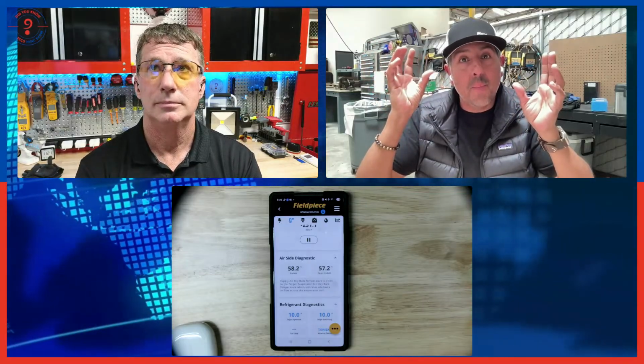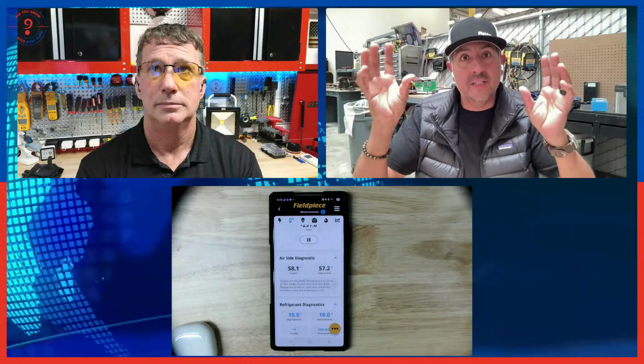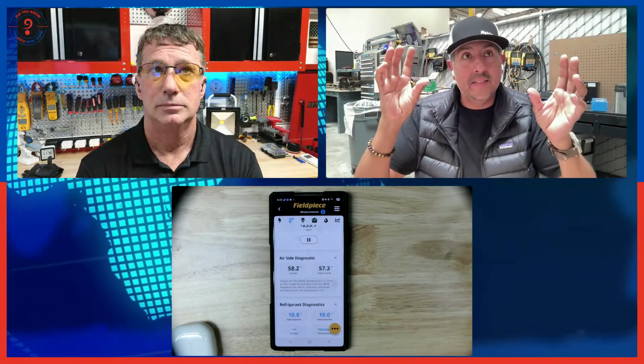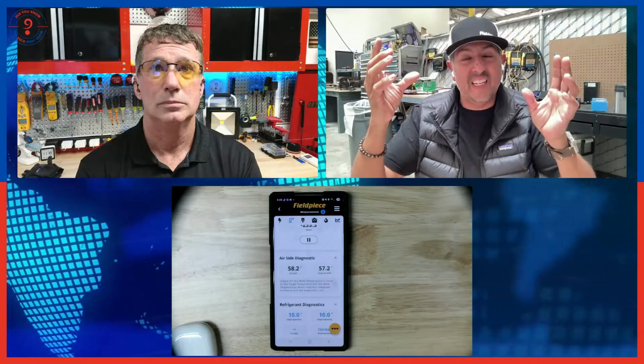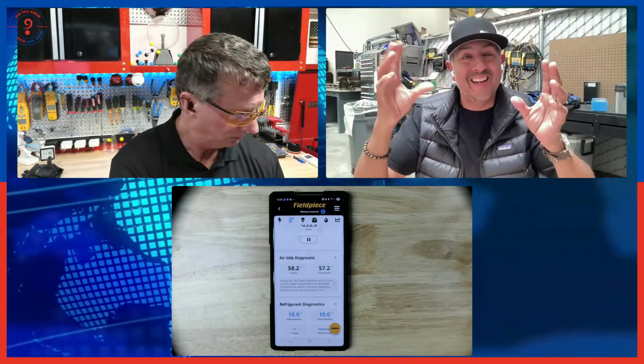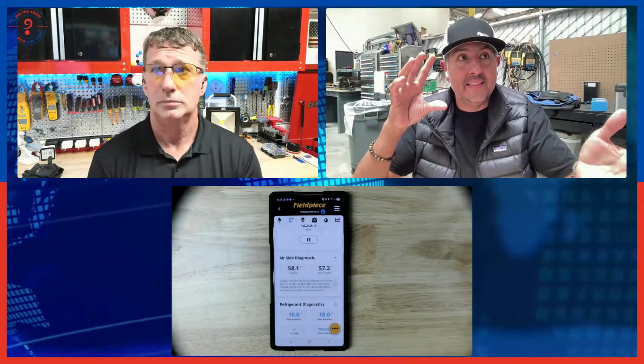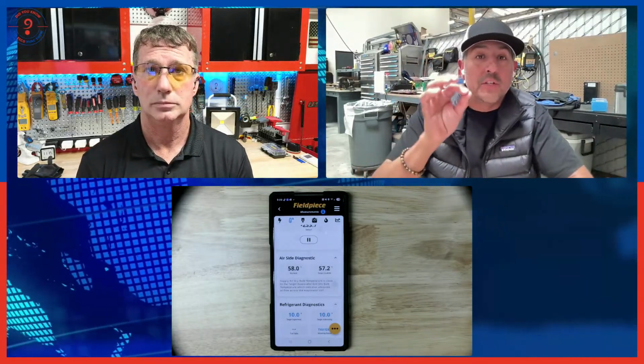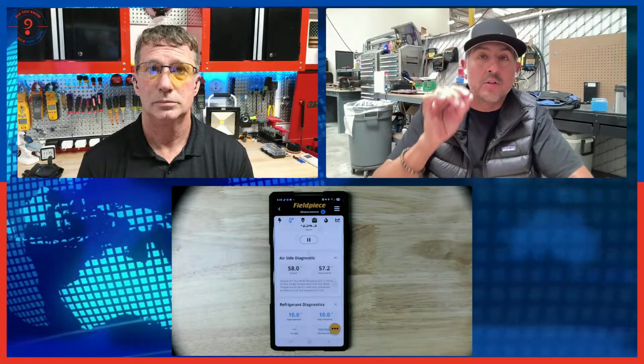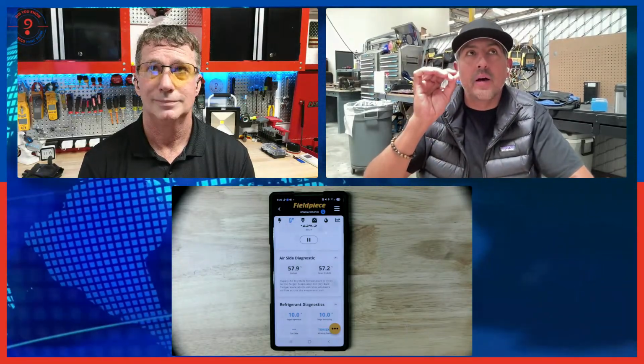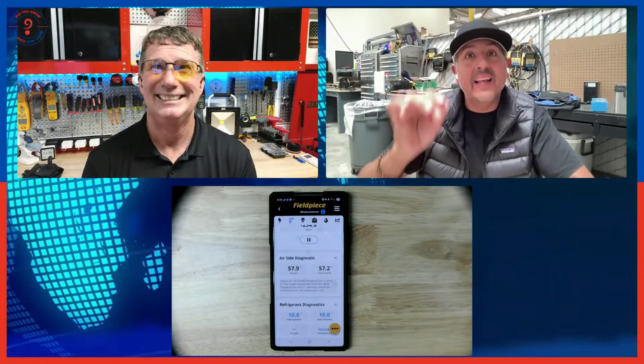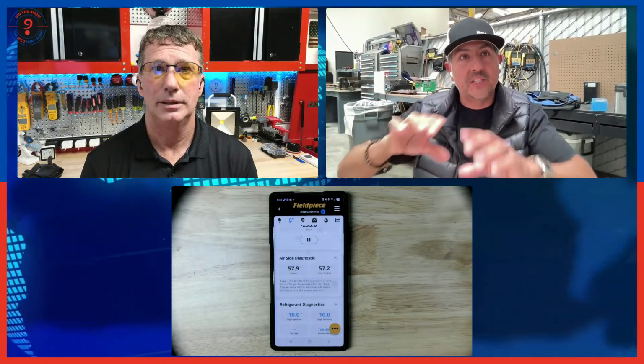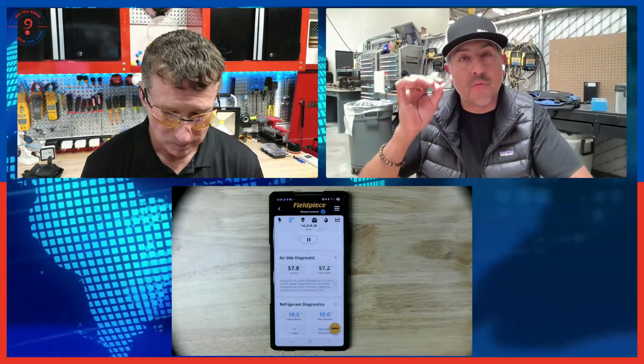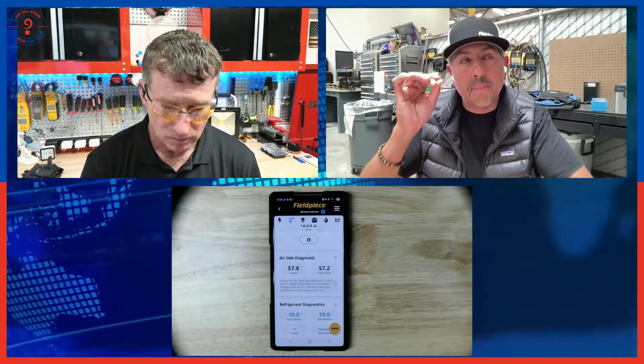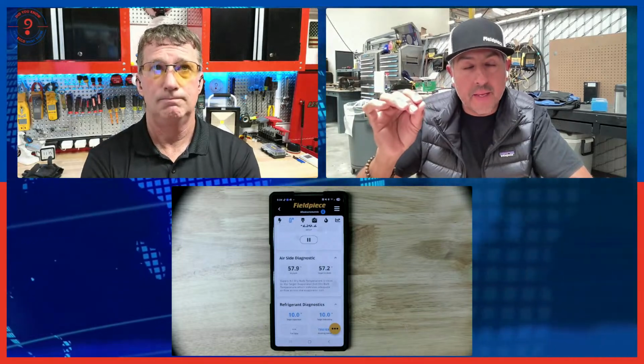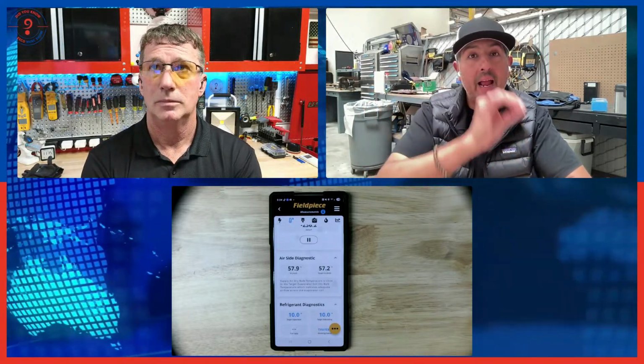However, that's not the be-all and end-all, because based on ambient conditions and conditions of that day, it is very possible that a 20-degree split is just not achievable, but that's not an indication that there's an issue with the system. So the gauge does a calculation called target evaporator exit temperature. That's just a long-winded way of saying it calculates what the supply dry bulb air temperature should be based on the return side air properties.